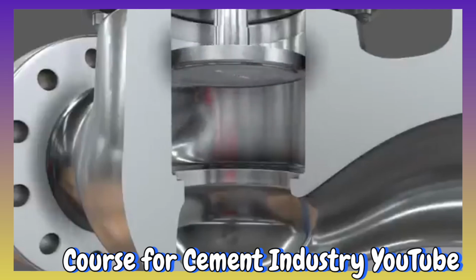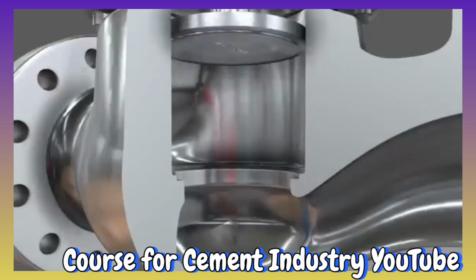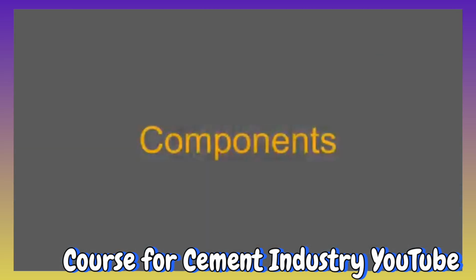valve. So this is different to a gate valve, where if we open the valve slightly, the amount of flow is not proportional to the opening and the flow velocity through the valve is very high. With globe valves we don't have that problem, and we can use the valve for throttling.